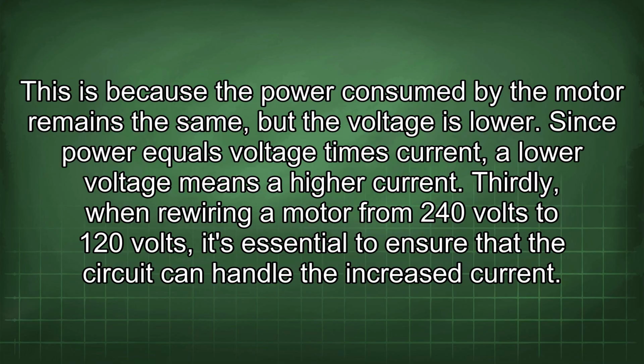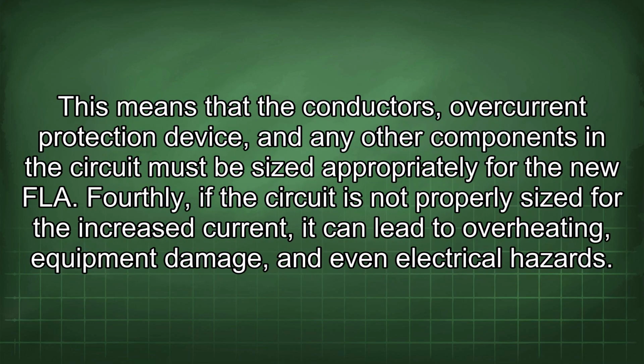Thirdly, when rewiring a motor from 240 volts to 120 volts, it's essential to ensure that the circuit can handle the increased current. This means that the conductors, overcurrent protection device, and any other components in the circuit must be sized appropriately for the new FLA.